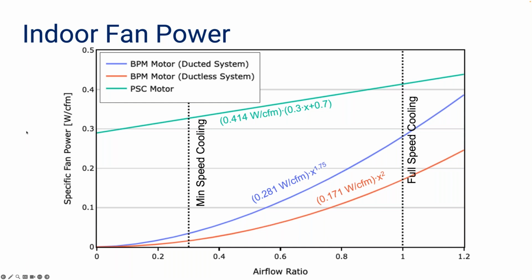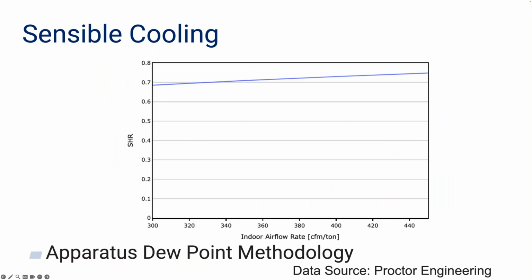And then we repeat the process using, instead of the AHRI rating points, the measured data from HVAC grading to establish a separate relationship based on the values measured. So these watts per CFM here are the assumptions that we have for the rating process, but those would be replaced with the values that are determined from HVAC grading.